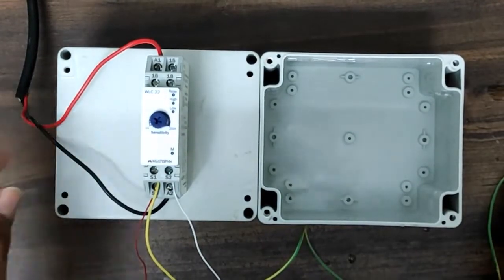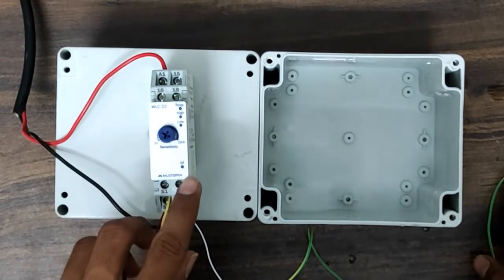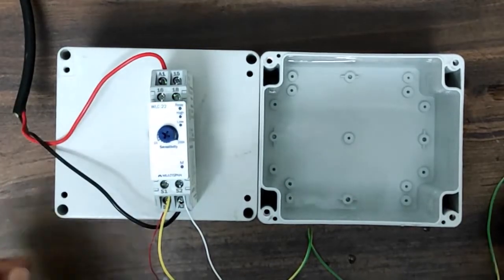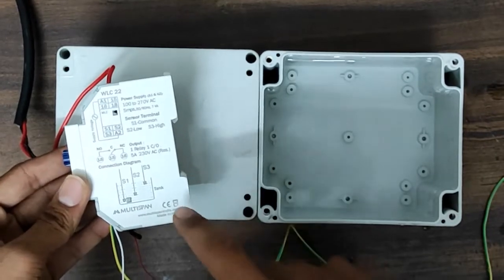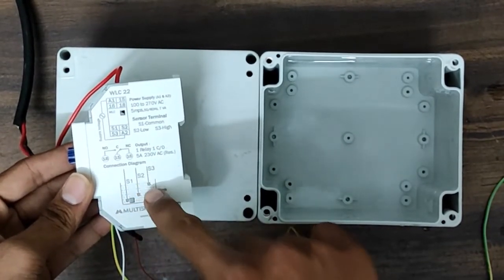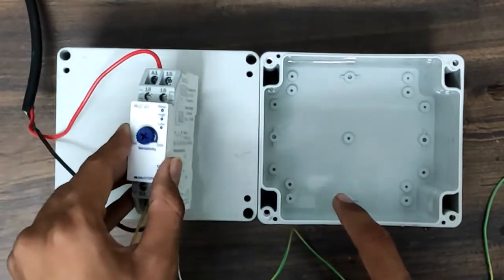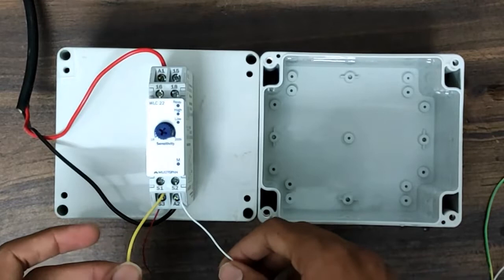Now you can see one setup with water and the controller — Multispan make, model WLC22. You can see here S1, S2, and S3 — three sensors available for water indication and controlling purpose. S1 is for common, S2 is for low, and S3 is for high. Now we will put S1, S2, and S3 inside the water.